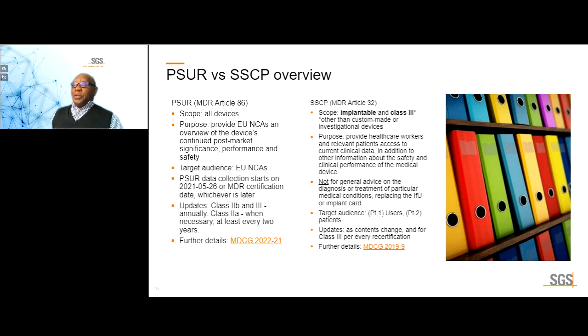The data should be collected from the day you have your MDR certificate. It should have also been from the date of application, but that is well gone now, 26th of May, 2021. And the requirement is for this report to be updated for Class 3 and 2B devices annually, and for 2A when necessary, but at least every 2 years. This is interesting. They're leaving it up to the manufacturer whether you choose to do this report every year for 2A devices or at least every 2 years. You can find further details in the guidance document MDCG 2022-21.